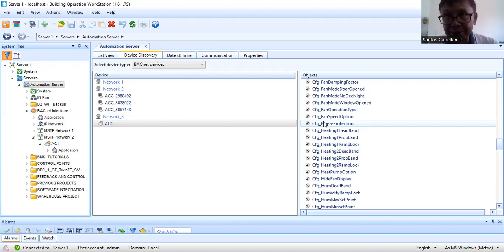Okay, so meaning if you submit your material submittal, it should include your proposed graphics for air coolers, showing all the points that you will get from the third-party system. Now it should be approved by the consultant, so that during testing and commissioning, there will be no more questions. If there is a question, what are these points? Is this approved? Yes, you have to show the approved material submittal.